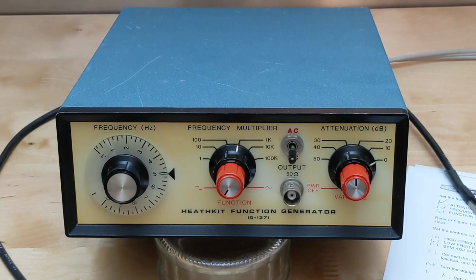The frequency multiplier control selects one of six ranges in decade steps from 1 to 100,000. The output frequency is determined by the frequency control, which goes from 0.1 to 10, multiplied by the frequency multiplier range. The lowest frequency is 0.1 Hz and the highest is 1 MHz. The variable attenuator knob turns on the power and adjusts the output over a 20 dB or 10 to 1 range. The attenuator control selects one of five ranges in 10 dB steps from 0 to 50 dB of attenuation. Output is taken from a BNC connector and has a 50 ohm output impedance.